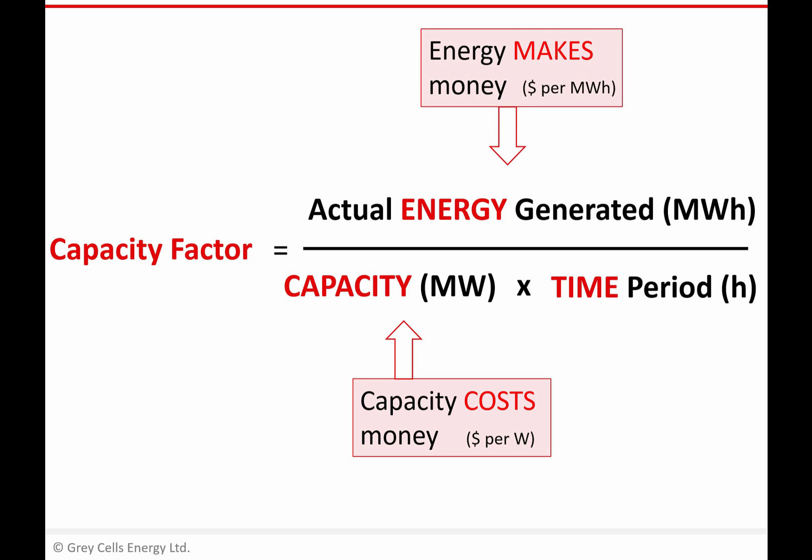On the top line, of course, it's generating energy that makes us money. We sell units of energy in dollars per megawatt hour. So on the top line of the equation, we've got energy which is making us money. On the bottom line, we've got capacity which is costing us money. From an economic point of view, the importance of capacity factor is that it's a ratio between something that's making us money and something that's costing us money.